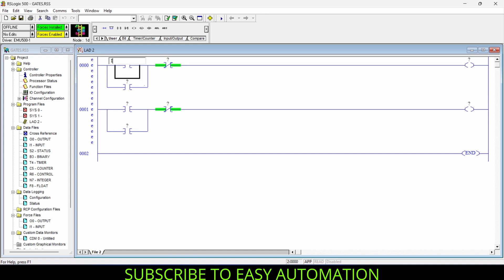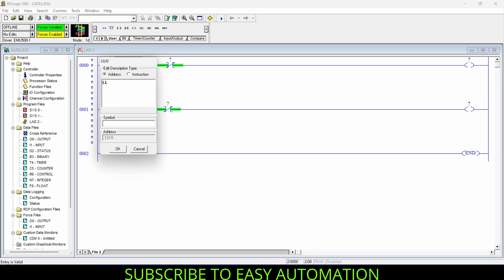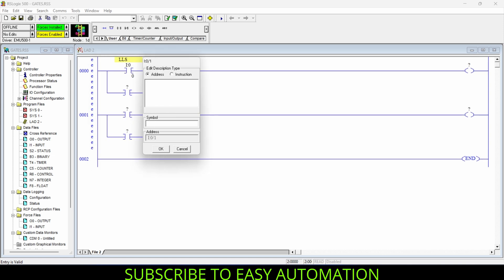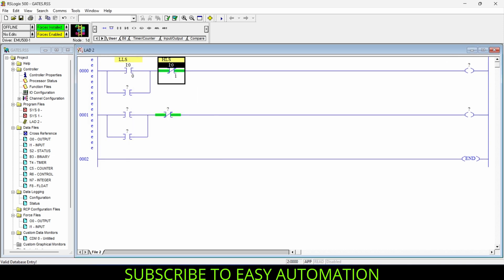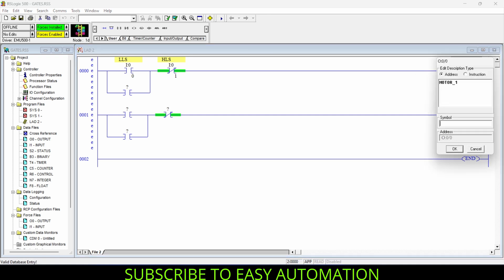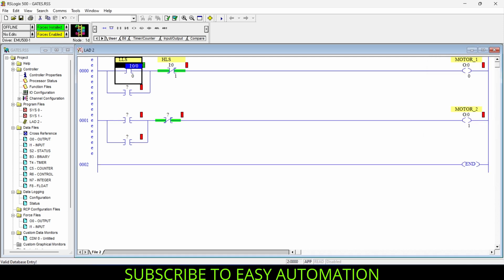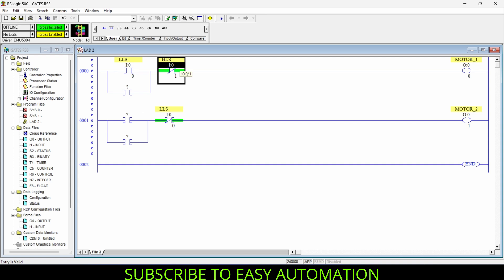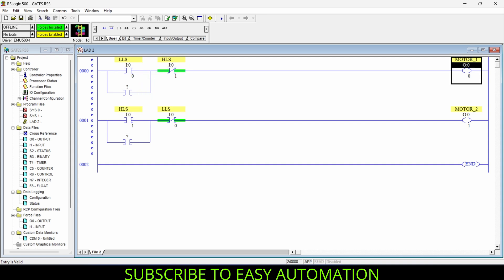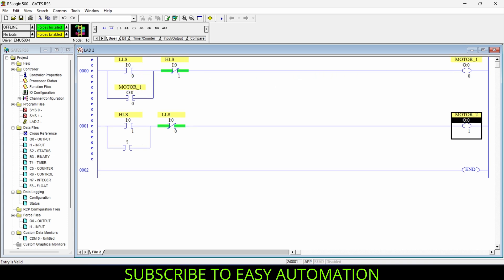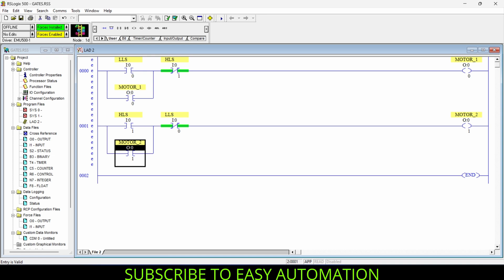Now let's give the addresses. I'll name the NO contact as Low Level Sensor (LLS), and the NC contact as High Level Sensor. The first output is named Motor One and the second output Motor Two. I'll copy the Low Level Sensor address to the NC contact of the second rung and the High Level Sensor address to the NO contact of the second rung. To create the holding, I'll copy the Motor One address to its NO contact, and do the same for Motor Two. Now our program is ready to be tested.